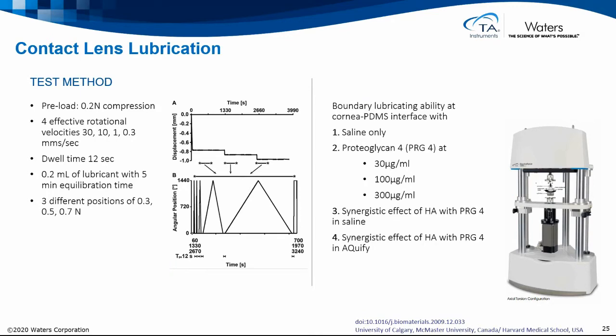So on the test method side, we see this combination of that linear motor on the top is programmed to do different forces. So that's like normal force in a friction equation. And then you're spinning that rotational motor below at different rates, and you can convert those to millimeters per second. And you can see this sequence of events, and the software allows you to sequence this both with sliding velocity as a variable and axial or normal force as a variable. So you can kind of do this all in one test experiment. And you can see the plots later will allow us then to pick apart these different variables. So that's how the test method is executed on this instrument.